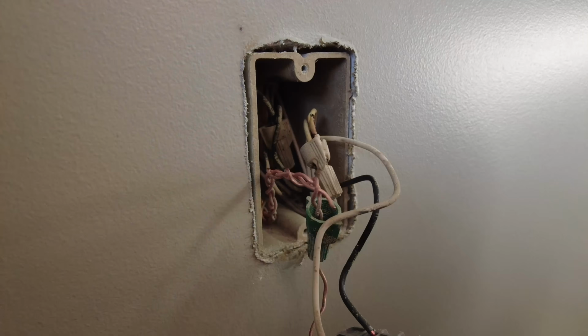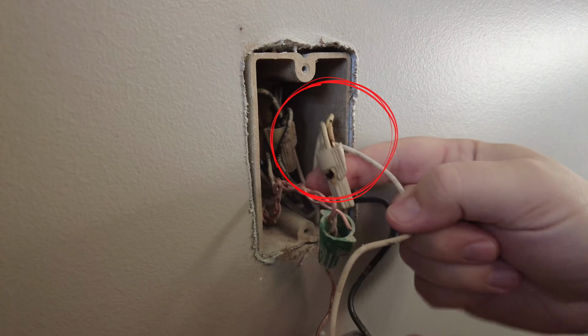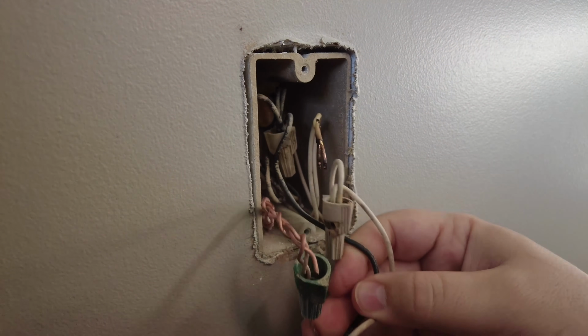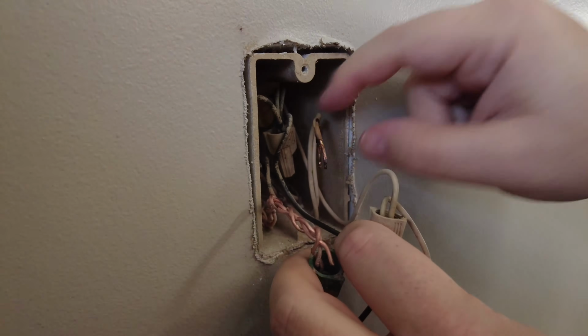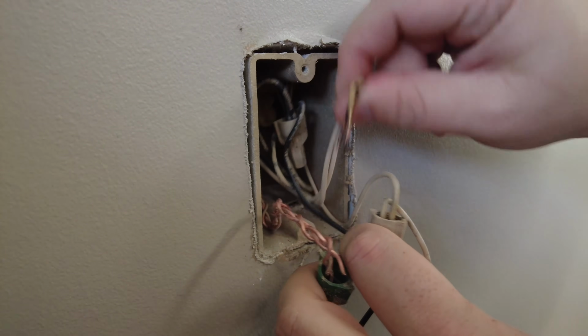Another really good indication that you might have a bad breaker is if you have appliances or electronic devices that misbehave or act really strangely when they're plugged into a specific circuit, and then they seem to be just fine if they're plugged into another area of the home. So that could be an indication of a bad circuit breaker. It can also be a sign that you have another electrical issue in that circuit as well. So it's a good idea if you notice some appliances or electronics that are not acting properly on a specific circuit to check out everything and make sure you understand and troubleshoot exactly what the problem is, but also don't forget to check out the breaker.